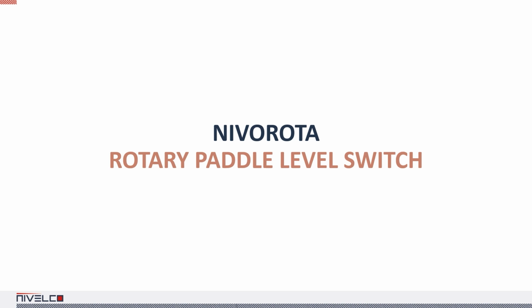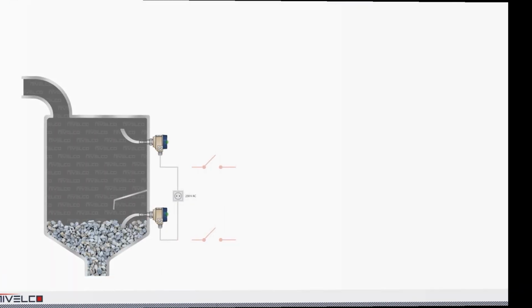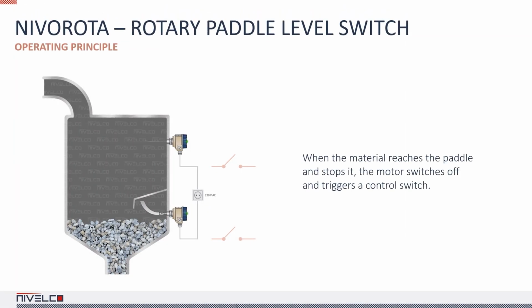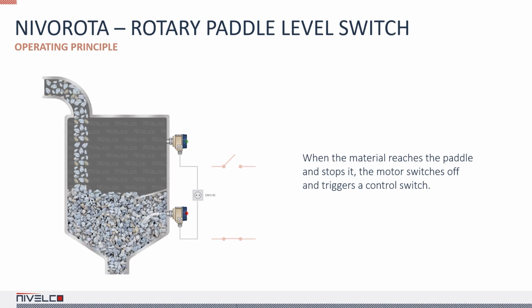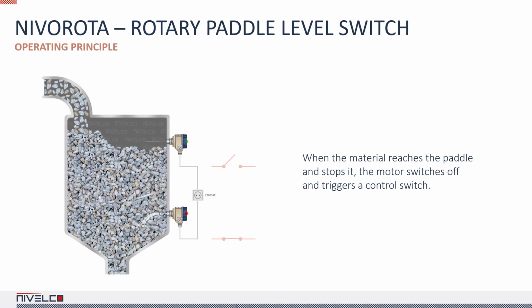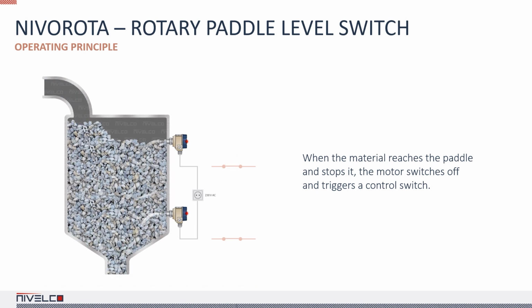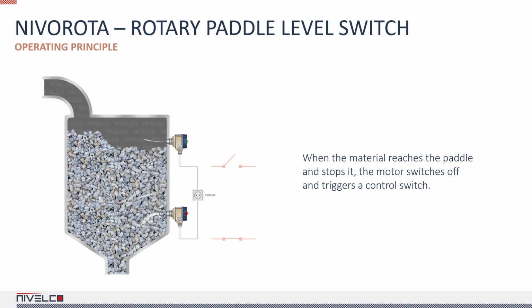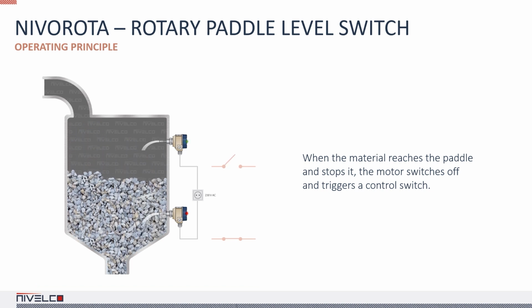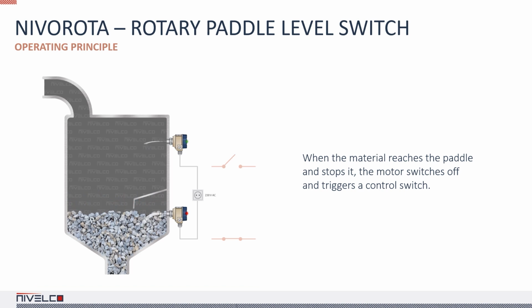Nivorota rotary paddle level switches detect the level of lumpy substances, powders, grains, and granules. A small electric motor drives the paddle, which rotates freely in the absence of the measured material. When the material reaches the paddle, the motor is switched off and the output switch is triggered. When the material level drops, the paddle is free to spin again. The motor is reactivated and the switch returns to its original state.